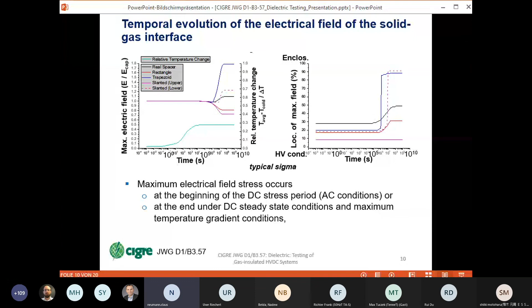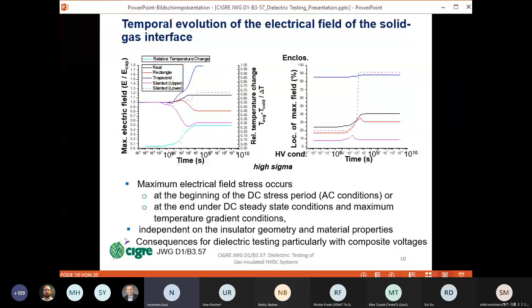That is true for typical sigma, but that's also true for high sigma, which can be used as another material parameter. That means it is independent of the insulator geometry, which can be derived from this figure here and from the material properties. And that has consequences for dielectric testing, in particular, if we take into account these so-called composite voltages. What are the consequences for these composite voltages? That means the superposition of the impulse voltage to the DC voltage, which should simulate the overvoltage stress during service.